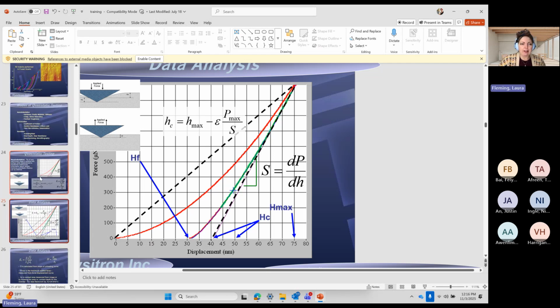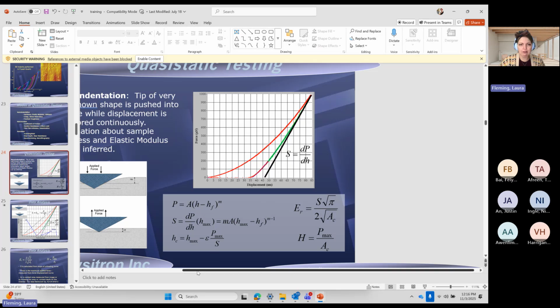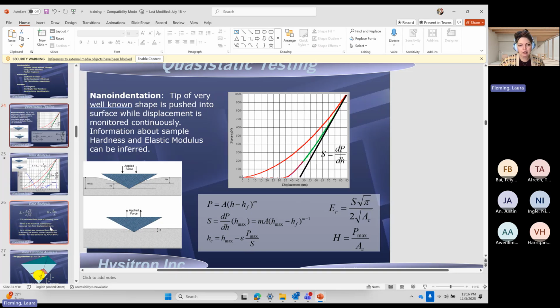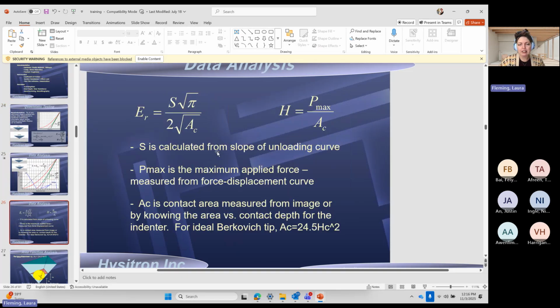Now, why does HC matter? So if we go back to this statement of a tip of very well-known shape, it has to be well-known because the reduced modulus and hardness are dependent upon the contact area. So what that means is that if you have a perfect pyramid, which is what an indenter typically is, which we can also talk about, all the different kinds of indenters and when you would use them, as you indent into the sample surface, if you take that pyramid and you cut it where the contact depth is, it's going to be a triangle. And from there, you're going to be able to calculate the contact area.